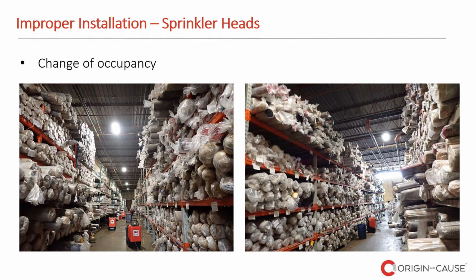In a case like this, look at this space here. It's a warehouse. It had a change of occupancy. It went from a warehouse that didn't have such a large fire load. So obviously, if you look at this, these are carpets, and there's a lot of them all the way to the ceiling. They had an issue with the system here, and obviously it got more complicated than just a couple heads going off.